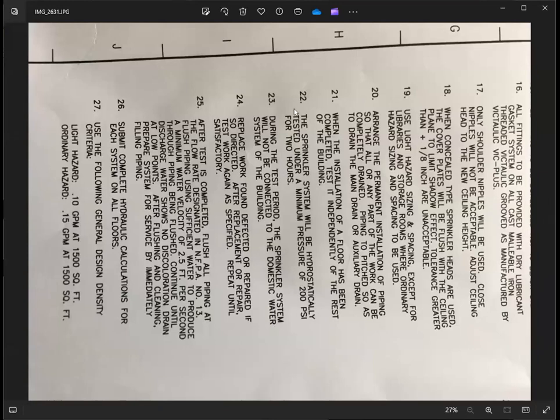Hydrostatically, you see, I took a photo of this. This is the requirement. The sprinkler systems will be hydrostatically tested under a minimum pressure of 200, minimum pressure 200 psi for 2 hours. So number 22, this is the requirement for the test. So minimum 200, so you need to be over or at least exactly 200.